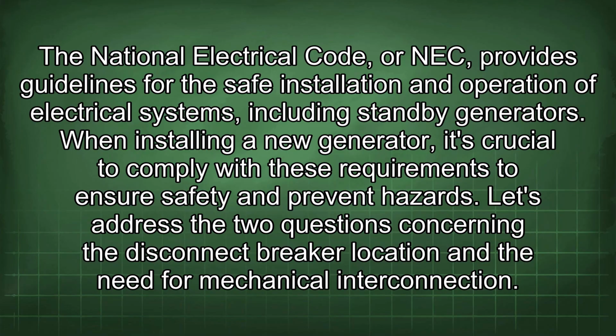The National Electrical Code, or NEC, provides guidelines for the safe installation and operation of electrical systems, including standby generators. When installing a new generator, it's crucial to comply with these requirements to ensure safety and prevent hazards. Let's address the two questions concerning the disconnect breaker location and the need for mechanical interconnection.